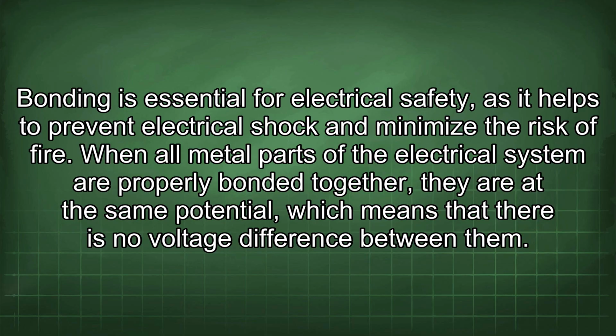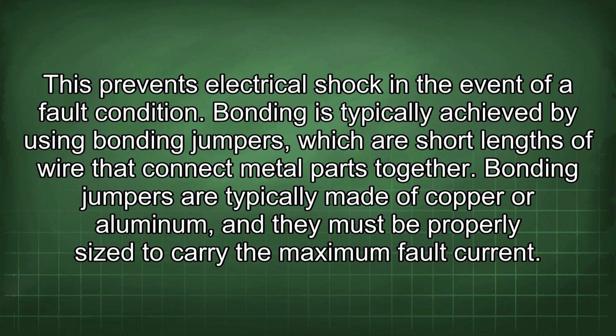Bonding is essential for electrical safety, as it helps to prevent electrical shock and minimize the risk of fire. When all metal parts of the electrical system are properly bonded together, they are at the same potential, which means that there is no voltage difference between them. This prevents electrical shock in the event of a fault condition.